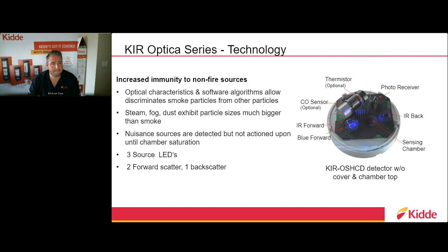Thanks for that question, because we've actually done white papers on college dormitories as well as hotels that have experienced issues with steam from showers or cooking. The device performed exactly the way it's engineered and designed, and the non-condensing steam was picked up by the smoke chamber and prevented a false alarm. That's significant from a life cycle cost savings standpoint—not so much for the product itself, but in cost savings for a hotel. Displacing hotel guests in the middle of the evening can be a significant issue for the hospitality space, as well as senior living, condominiums, multifamily, and dormitories. A false alarm due to a cooking source or steam can be a real problem.